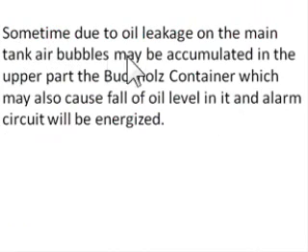Sometimes due to oil leakage in the main tank, air bubbles may be accumulated in the upper part of the Buchholz container which may also cause fall of oil level in it and alarm circuit will be energized.